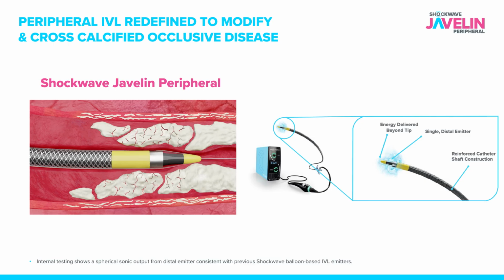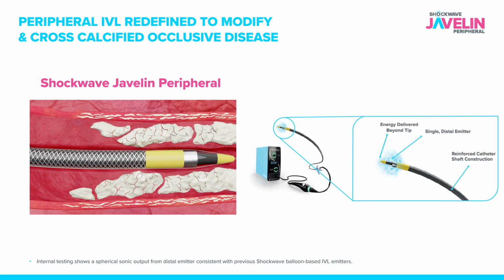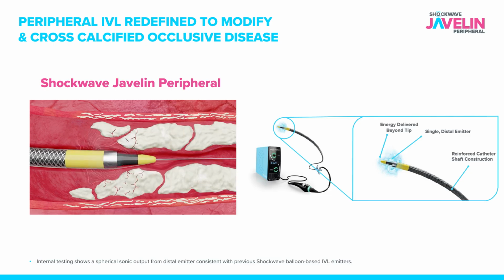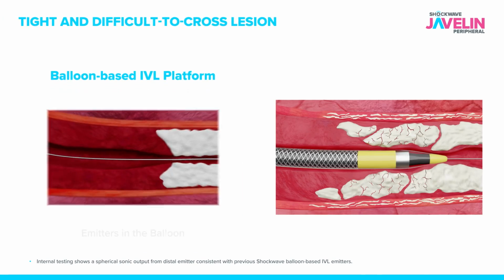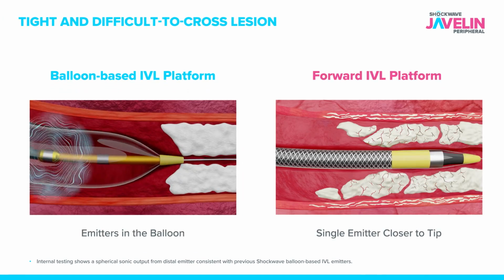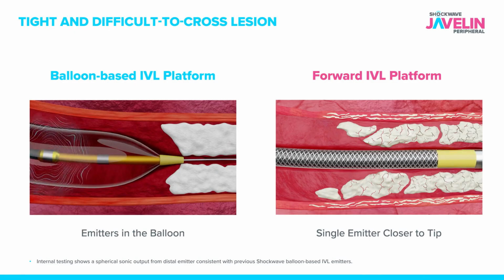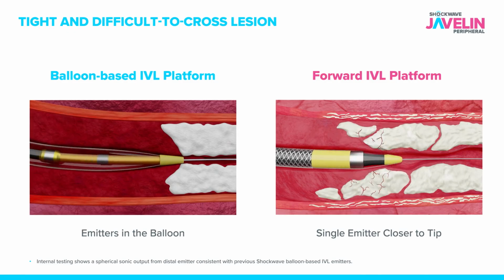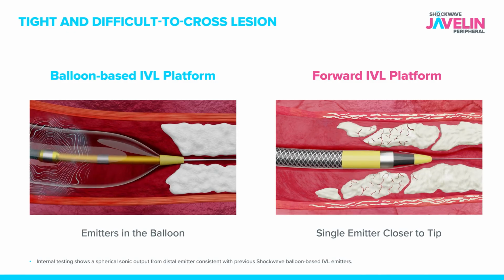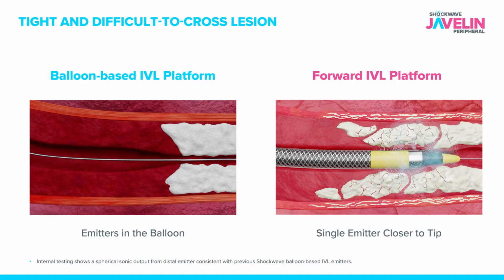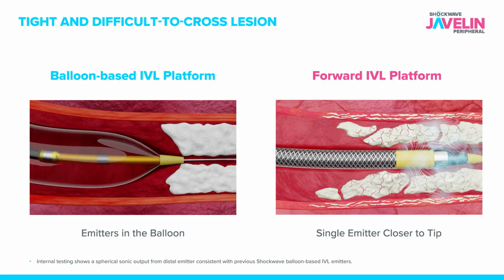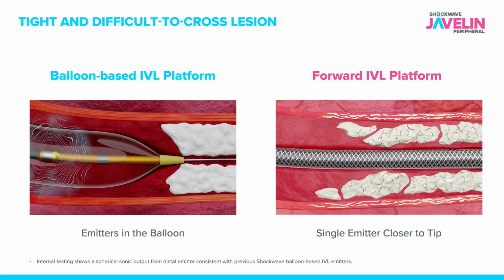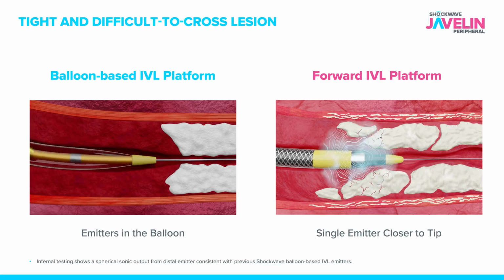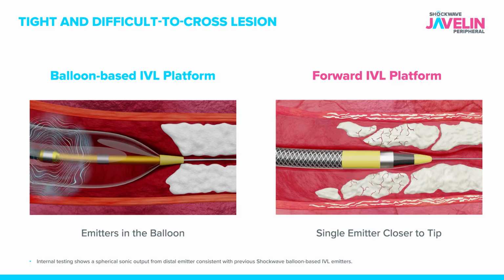The tip of the catheter has an emitter which is 3 millimeters from the tip. It can extend the energy profile beyond the tip to help modify that calcium and assist in crossing. You'll see in this video the standard balloon-based lithotripsy catheter. The distal emitter is not close enough to the tip to affect the calcium to allow crossing of that device. You can see the Javelin catheter with that forward-shifted emitter can modify the calcium even out in front of the tip to assist in crossing.